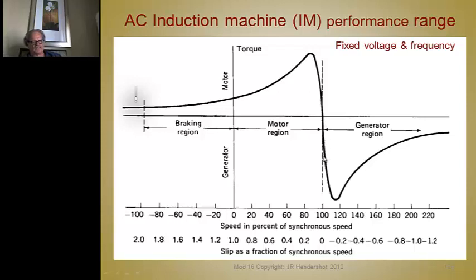You have a negative slip instead of positive slip, but only up to a certain point, and then it'll stall as well. It may not stall the prime mover, but it'll apply. The torque will go up quite high, and then the torque goes way down, of course, as you go faster and faster. So as a generator, you'd never speed it up past maybe 105, 110% of synchronous speed. You'd never operate a generator down this range. It's crazy.